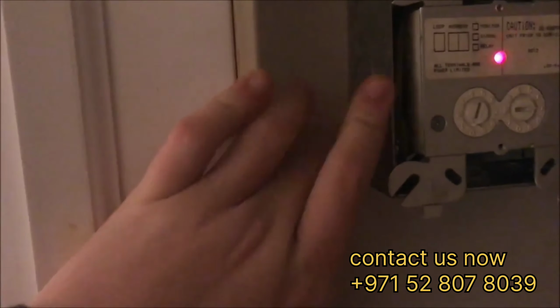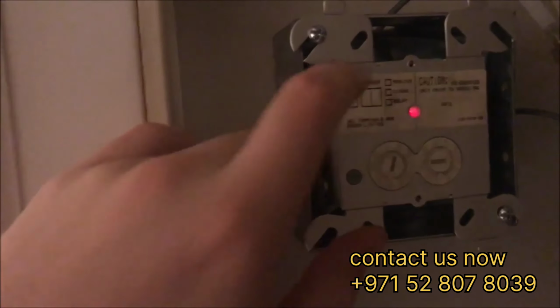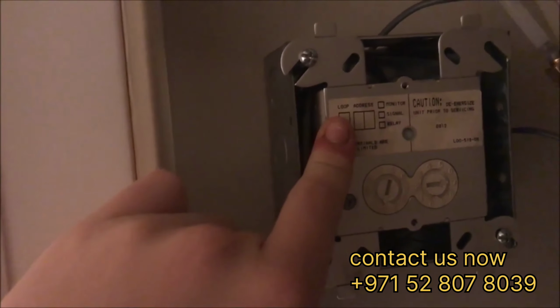I have one in the closet here. So this is just a Notifier MMX1. This is a monitor module for my Notifier AFP. You can see it is set to 07 because I have it set to 7. Some use rotary switches like this, some use dip switches. It's all up to the manufacturer.